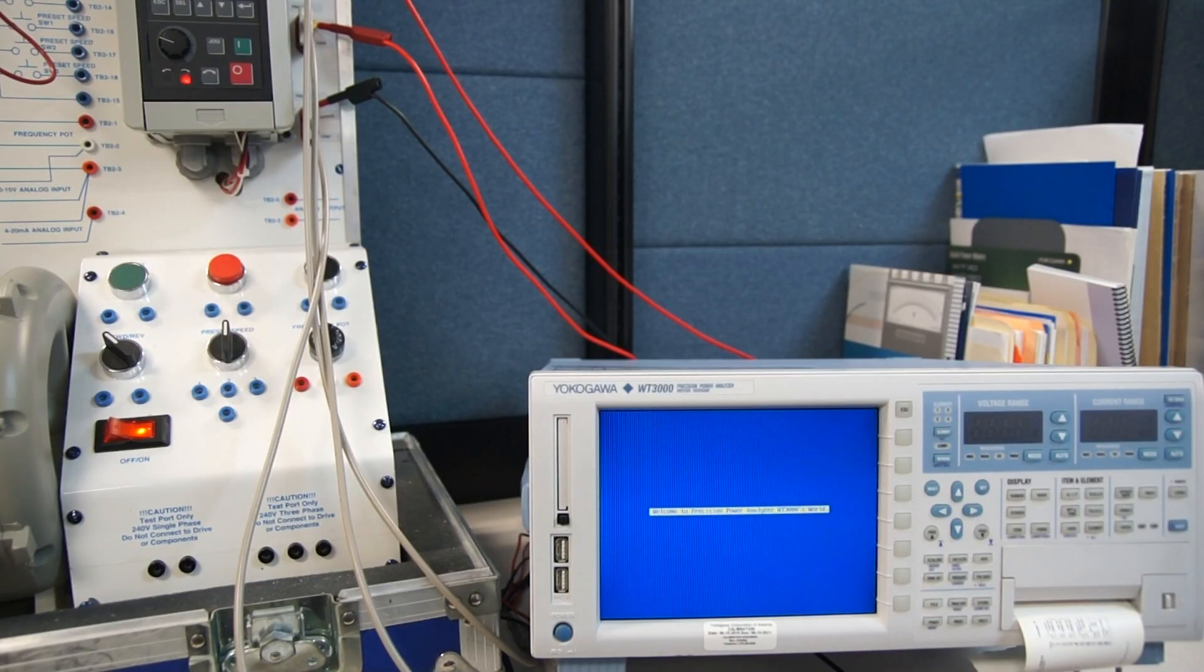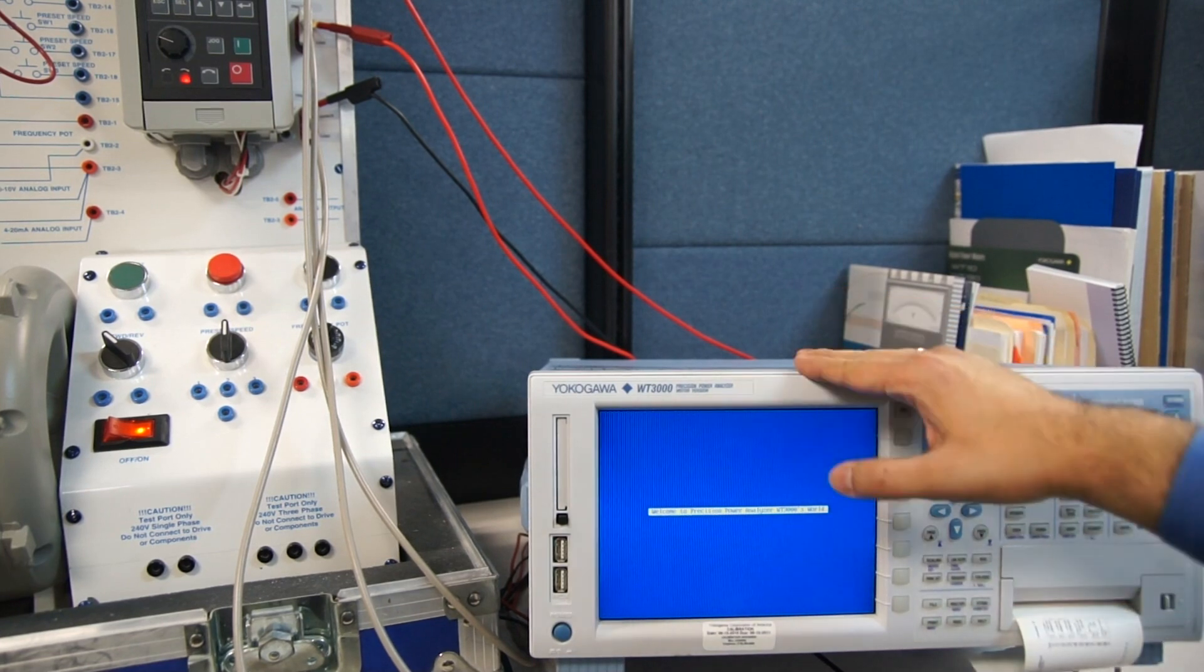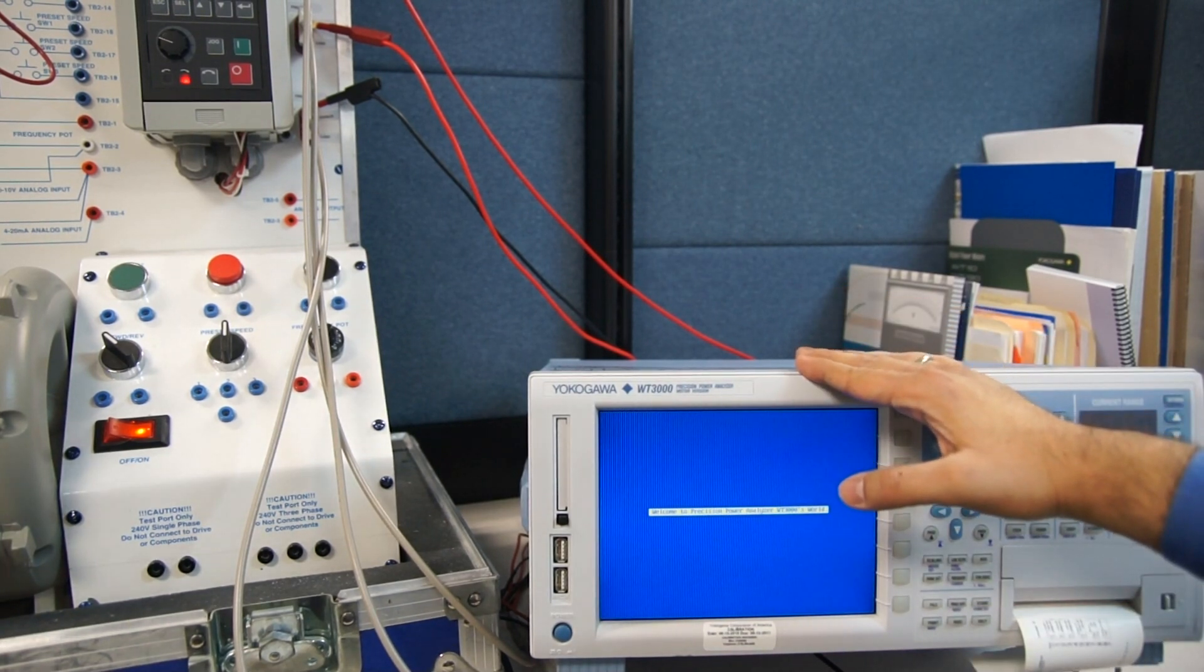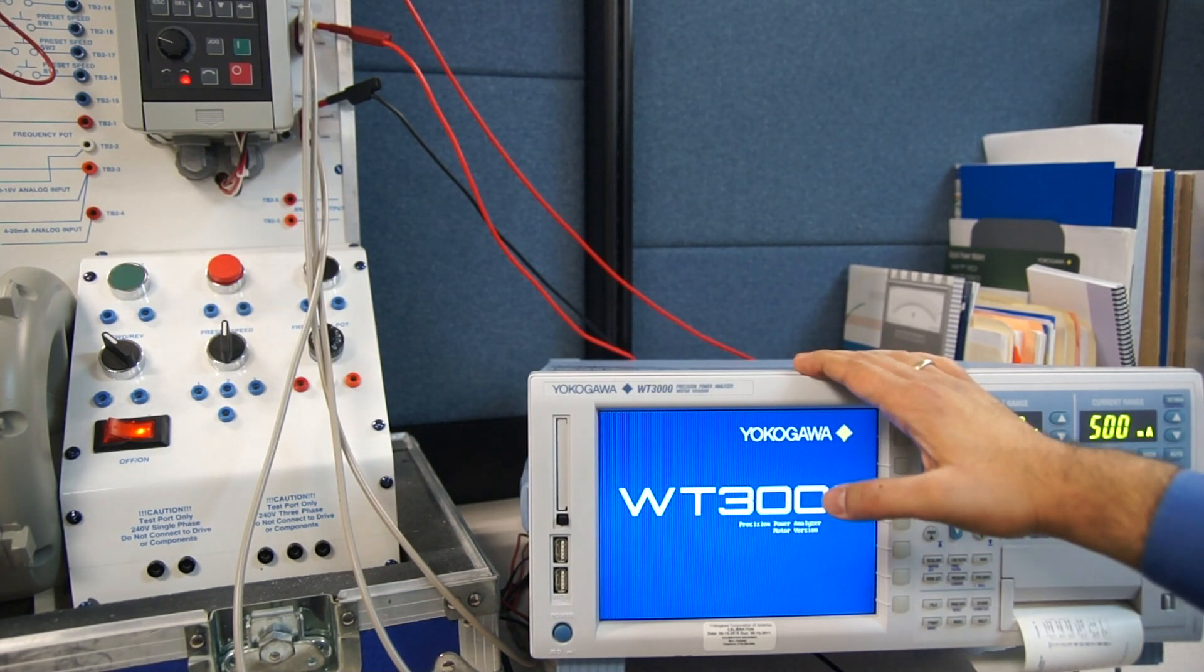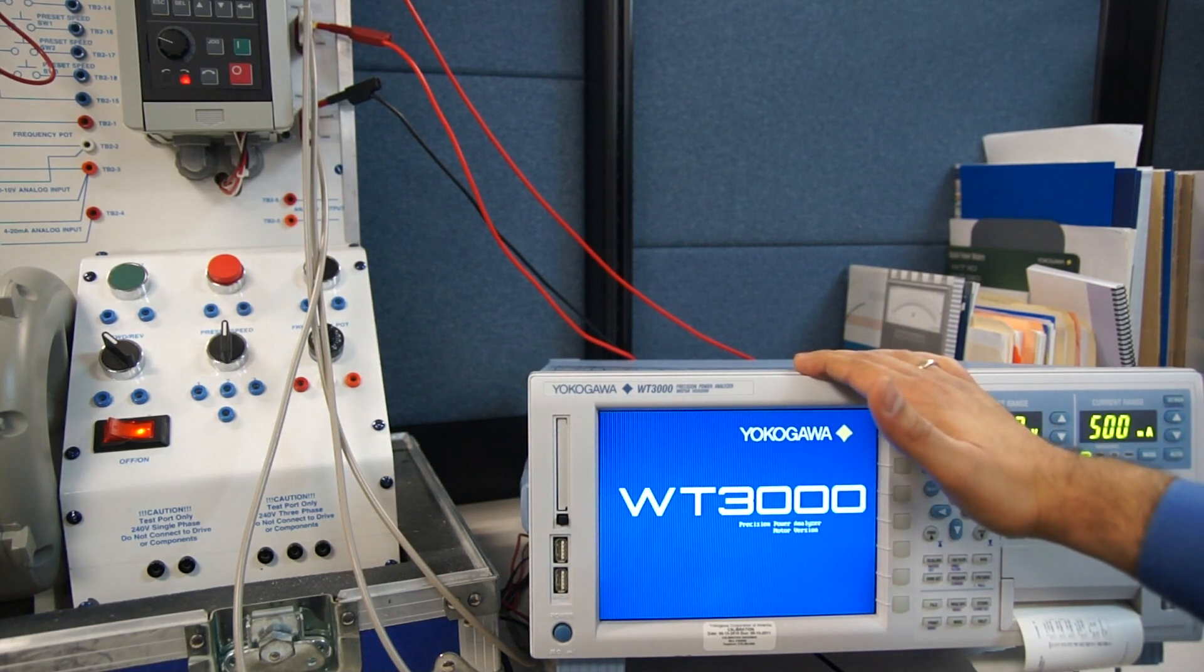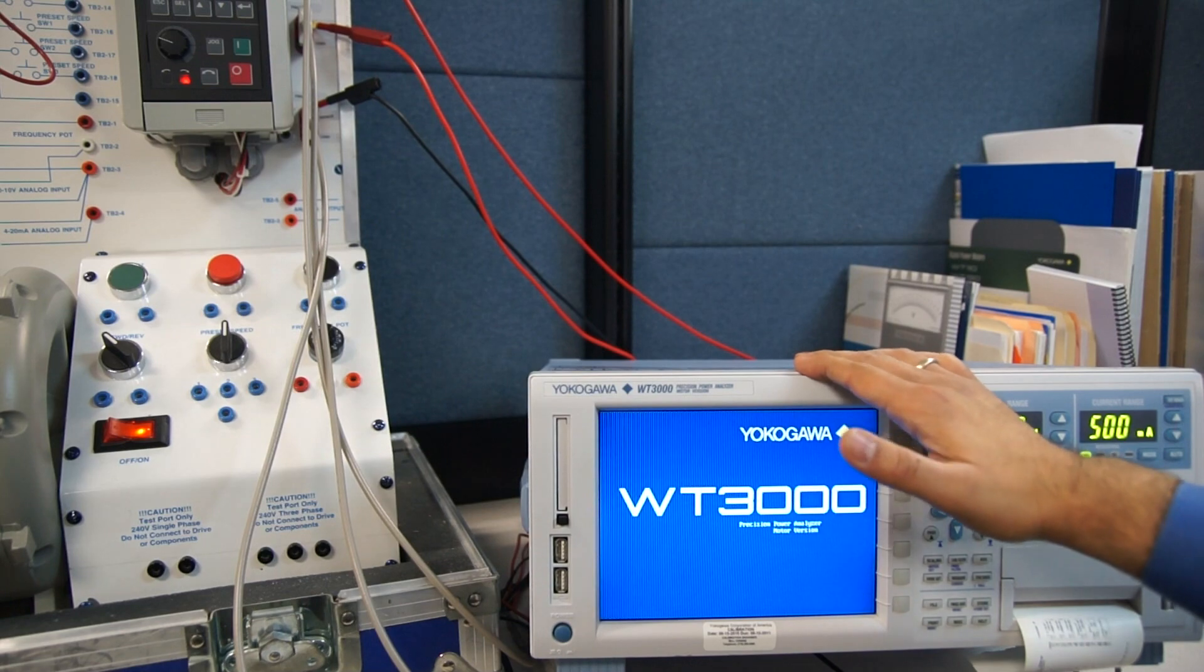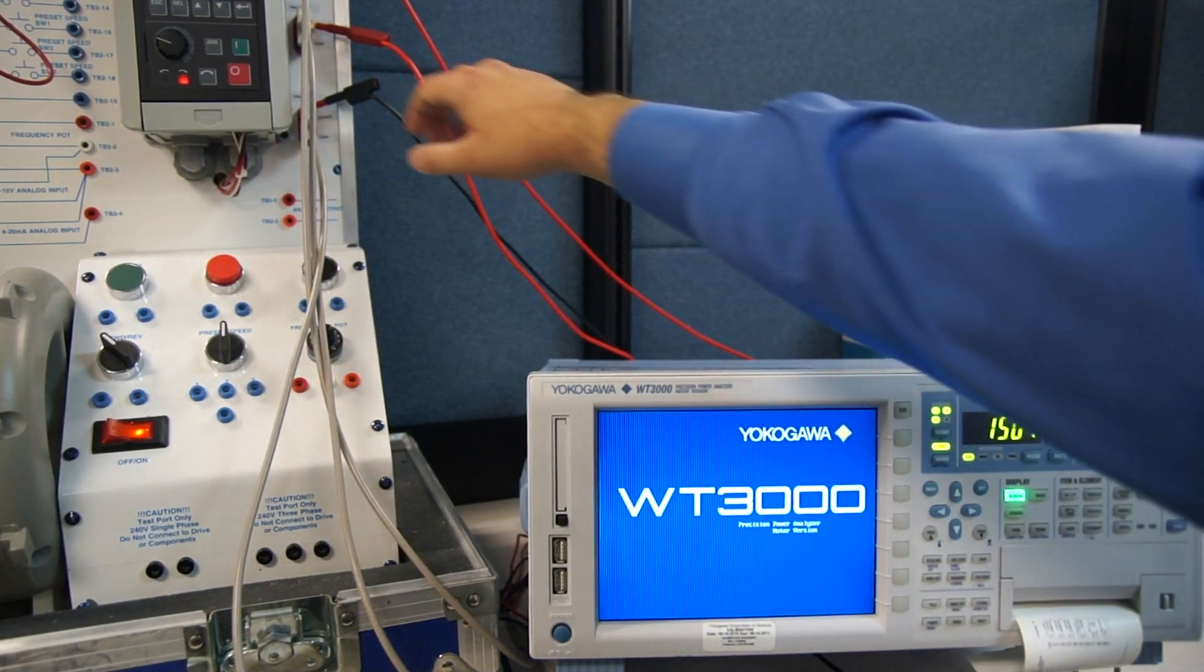So now that we have connected our three-phase three-wire circuit to a power analyzer, let's go ahead and turn the power analyzer on and verify if all our voltages, currents, and power are reading correctly. Also, we will verify if all the power is positive, which tells us that our wiring is correct. So let's go ahead and turn the motor on.